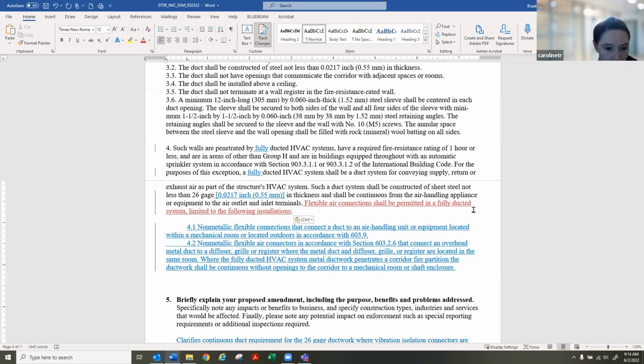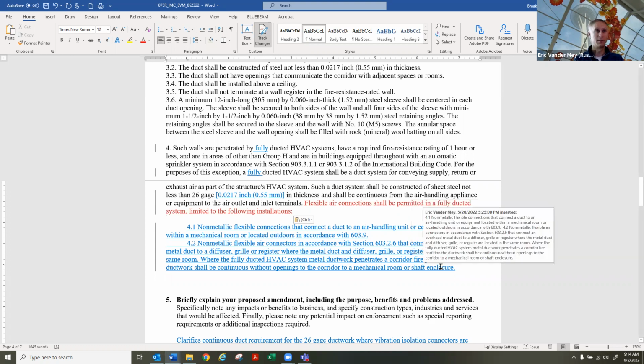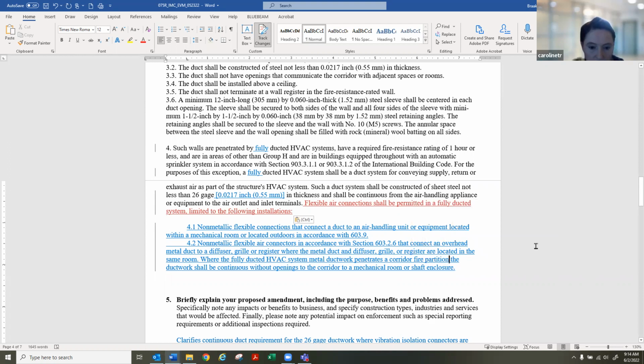And then that very last sentence added in 4.2. Does it need just like a comma or something? So where the fully ducted HVAC system metal ductwork penetrates a corridor fire partition, the ductwork shall be continuous without openings to the corridor, comma, to a mechanical room, comma, or to a shaft enclosure. Is that the intent? Without openings, maybe it'd be better to say without openings in the corridor, or I don't. So I was just proposing a comma, Krista, after the word corridor in that last sentence. Yeah, you're right. You need some help. Next corridor. There's a corridor like 6 words from the end or something. Yeah, and then a comma after the word room, and then.